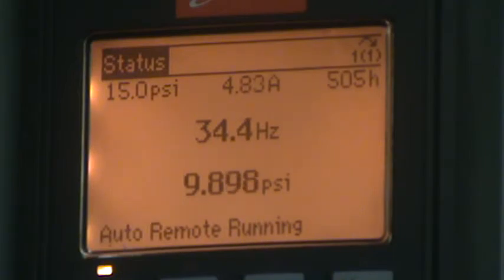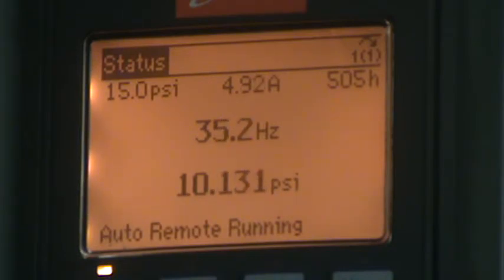When we walked in here this morning, was it set at 15 PSI? No. They were on manual? No, they were running in hand just at a generic speed. Okay. So we don't know what the actual PSI should be for this building. We don't know the design. There was no designed pressure differential given to me. Right. So that's why I'm saying the 15 PSI is just kind of an educated guess. And you guys are going to have to kind of fiddle with that until you get what works for the building.